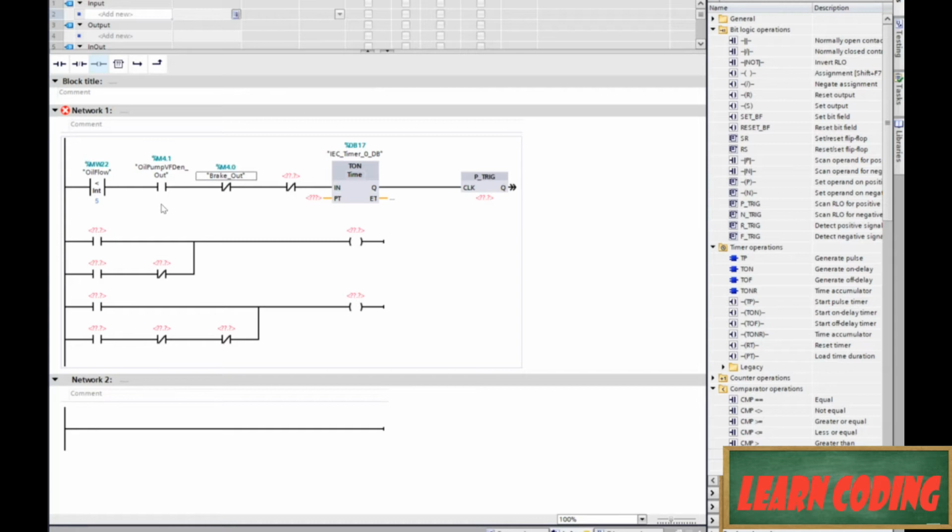Okay, so what does this mean? If the brake's not engaged, that means the generator's free to spin, and if it's on a river, of course it's going to be spinning. And maybe for some reason we've got the oil pump disengaged, in which case we're not worried about an oil flow problem. We might have other problems, but it's not low oil flow. But while that thing's spinning, and the VFD's engaged, that means we're probably running, and that means we should have greater than 5 gallons per minute.